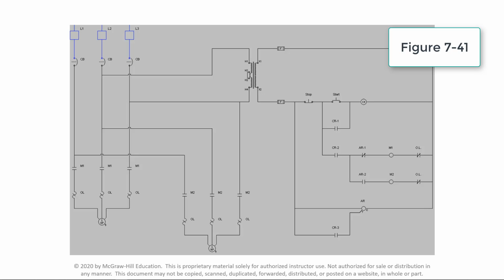When the pump stop button is activated, the first load, M1, is turned off and the alternating relay toggles to the M2 operating position. When the circuit is again activated, it energizes the second load, M2. When this sequence is repeated, this process is repeated again.